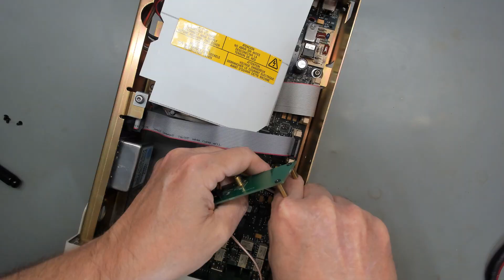That brings it down under 225, and then in the firmware, the processor knows how many times it's been counted, so it just does a multiplication. So it's a very simple operation. It's not complicated in any way. It's straightforward. You do lose some resolution, obviously. You don't have quite the resolution you do at the lower frequencies, but with the resolution this counter has, you can give up a little and still have a really good setup.